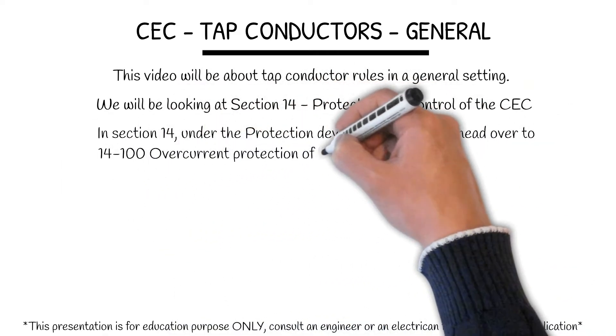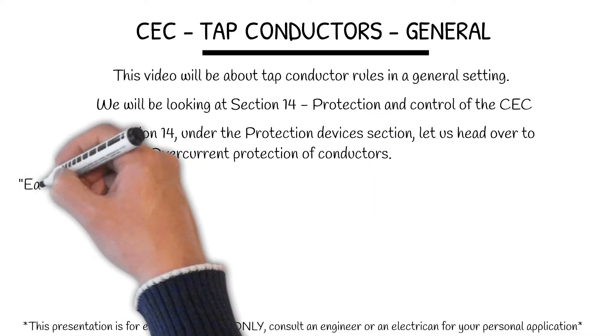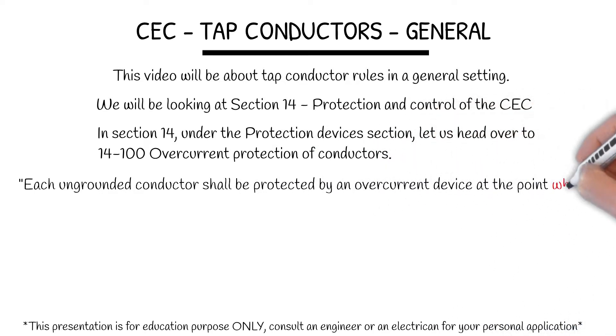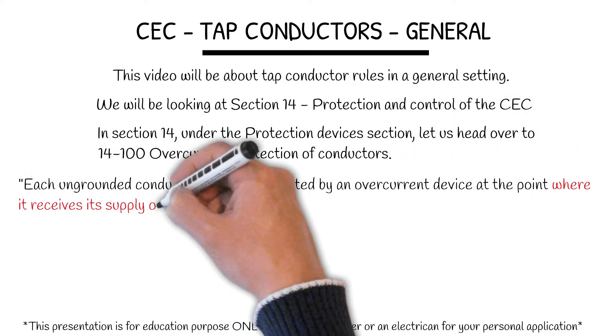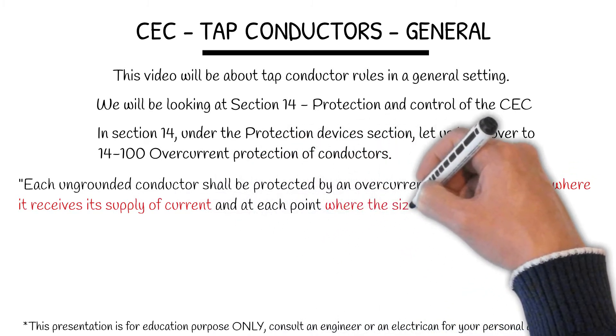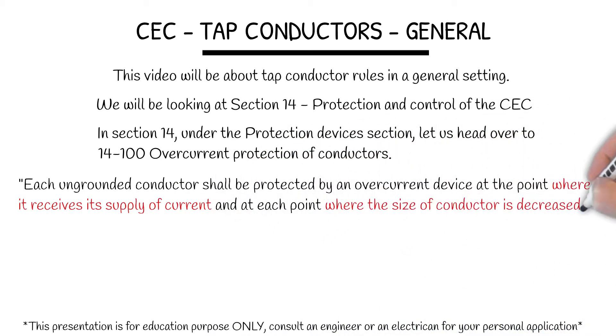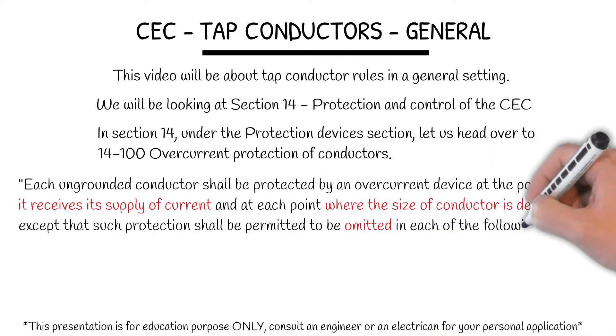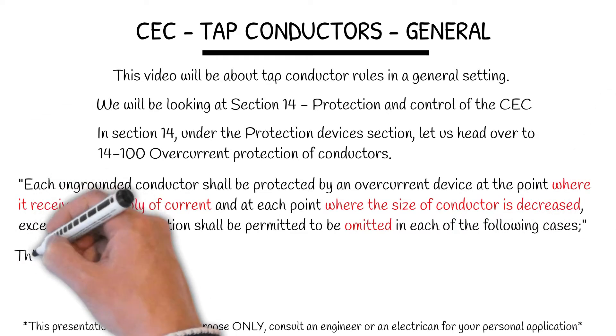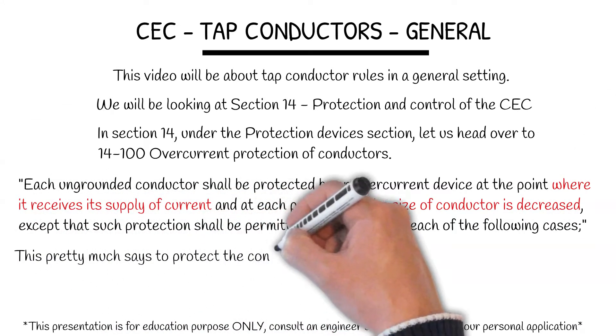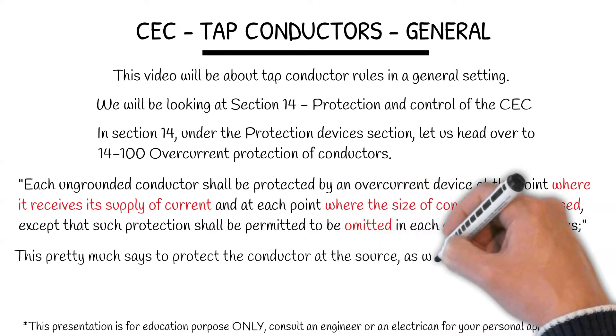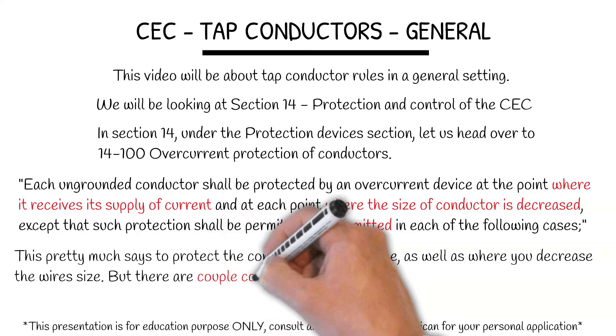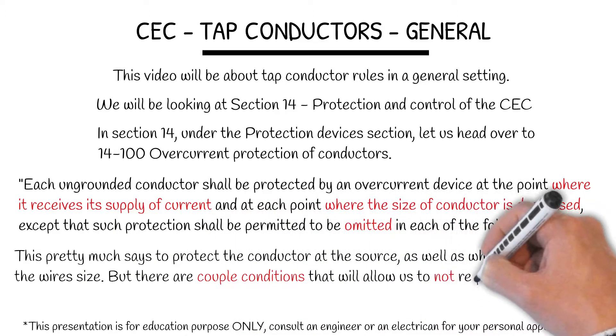Each ungrounded conductor shall be protected by an overcurrent device at the point where it receives its supply of current and at each point where the size of conductor is decreased. Except that such protection shall be permitted to be omitted in each of the following cases. This pretty much says to protect the conductor at the source as well as where you decrease the wire size, but there are a couple of conditions that will allow us to not require an overcurrent device.